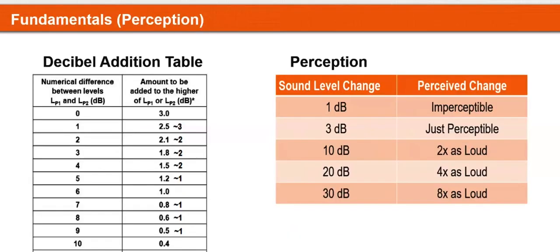A couple other pieces of theory to remember, specifically on perception and sound addition: the human ear cannot perceive changes lower than 3 decibels. Doubling of power is a 3 decibel increase, so the power needs to double for us to sense that change. However, a 3 decibel increase is not perceived as twice as loud. A 10 decibel increase is what we perceive as twice as loud, or a 10 decibel reduction is half as loud.